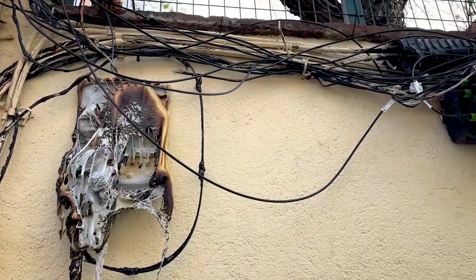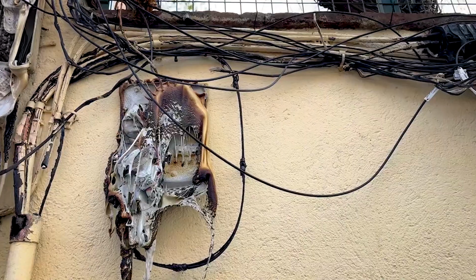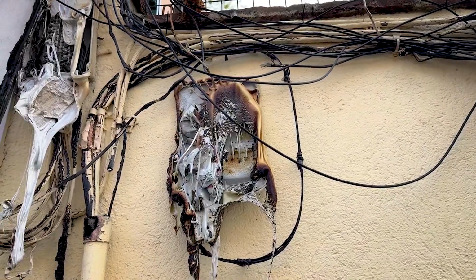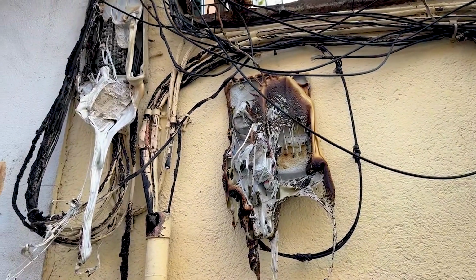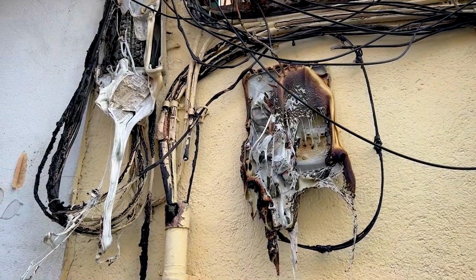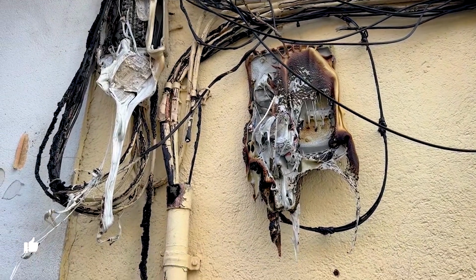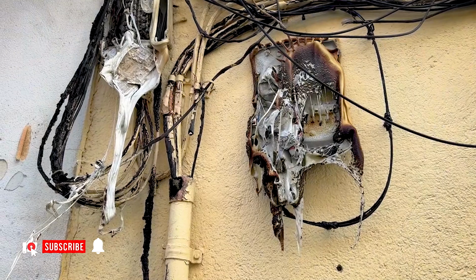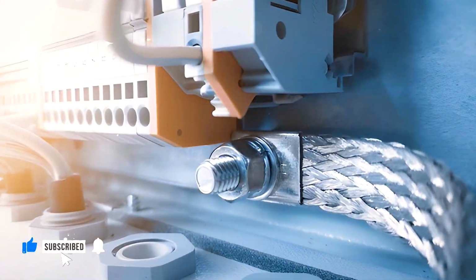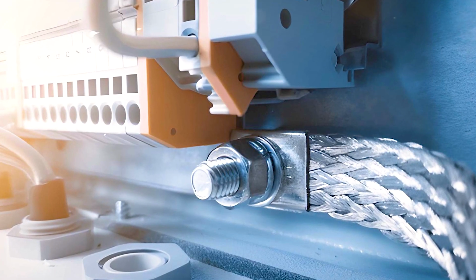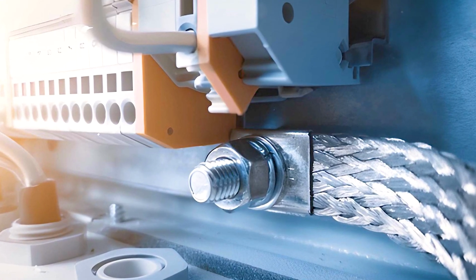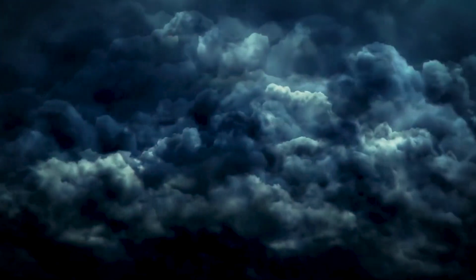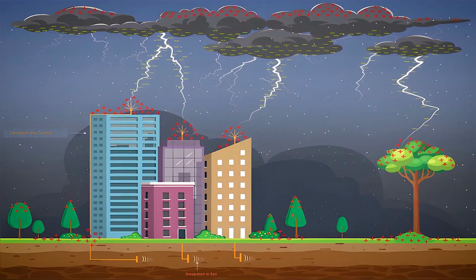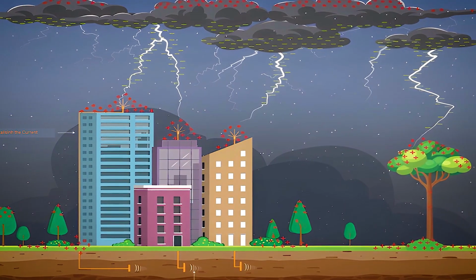Beyond shock protection, grounding also plays a vital role in fire prevention. Fault currents that are not safely diverted can generate excessive heat at unintended points, gradually degrading insulation and igniting nearby combustible materials. Proper grounding stabilizes system voltage, limits overvoltages, and provides a discharge path for transient surges caused by lightning strikes or switching operations, which are common sources of electrical fires in both residential and industrial environments.